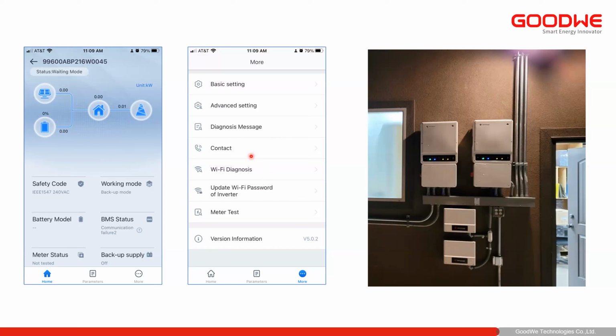Pictured on the right are storage inverters, each one with their own auto transformer, which derives a neutral when you lose a grid. I didn't get into that detail because I'm avoiding talking about energy storage—I want to focus on the PV inverter. But you certainly could have two PV inverters that look just like this side by side, or more. You can have multiple PV inverters feeding into the same panel as long as you have the amperage overhead in that panel.